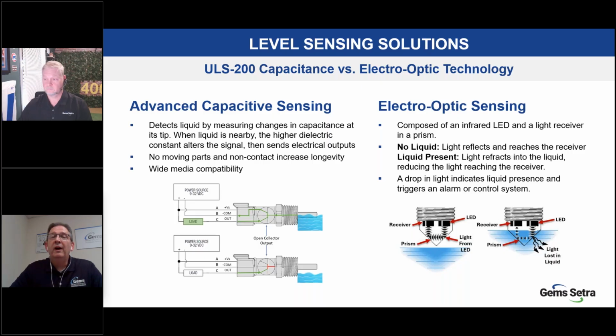Slightly different, but similar, on the optic side we use light to detect presence or absence of liquids. We emit a beam of light, bounce it off a prism, and it returns to a receiver. When there's no liquid present, the full signal comes back. But as it's immersed in liquid, some light rays are refracted into the liquid, so a lower intensity beam returns, and the sensor is smart enough to sense that and know it's wet. So if you're looking for presence of coolant, it'll tell you when it's wet. If you're watching for loss of coolant, it'll change back to its normal shelf state, telling you by the presence of the full light beam.